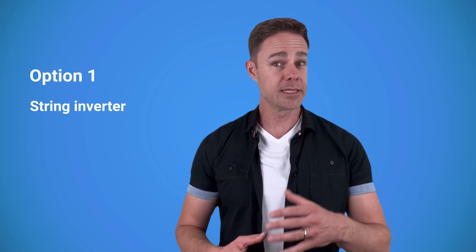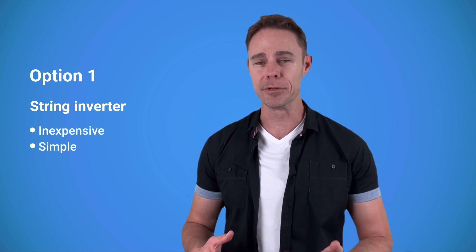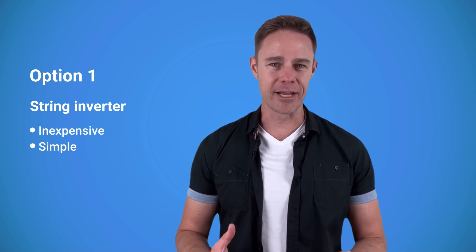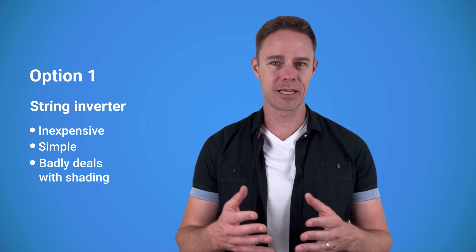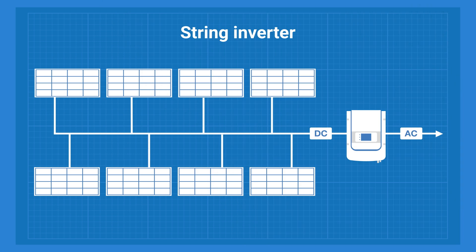The only real downside of a string inverter is how badly it deals with shading. Let's say you have several panels connected to each other - this is a string. When one panel gets shaded, the string inverter brings the production of every panel in a string down to the level of the worst one.